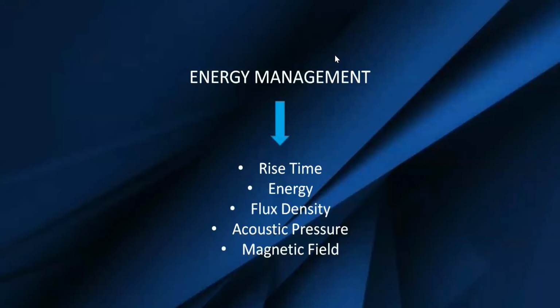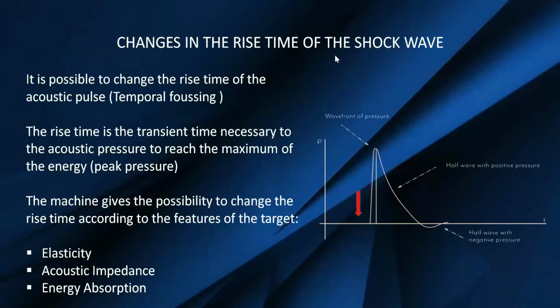The more important aspect of the CTU shockwave machine is the possibility for the operator to manage the distribution of the energy in the focus. As explained by Federica, we can modulate the rise time of the shock waves, in accord with the elasticity, the acoustic impedance, and the energy absorption of the tissues.